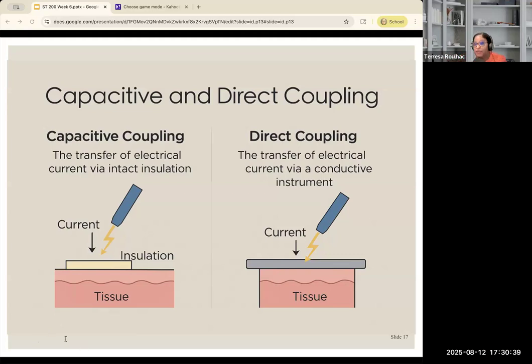Now, direct coupling is slightly different. If you look, it tells you it's going through the insulation, it's peeking out. Now, for direct coupling, okay, the current jumps from one conductive object to another, from an active electrode to a metal instrument, without passing through the tissue. Now, how does this happen? Defective insulation, or contact between the electrode and another metal object, or even placing the electrode inside a conductive metal sheath by mistake. This again can cause unintended burns or tissue damage.